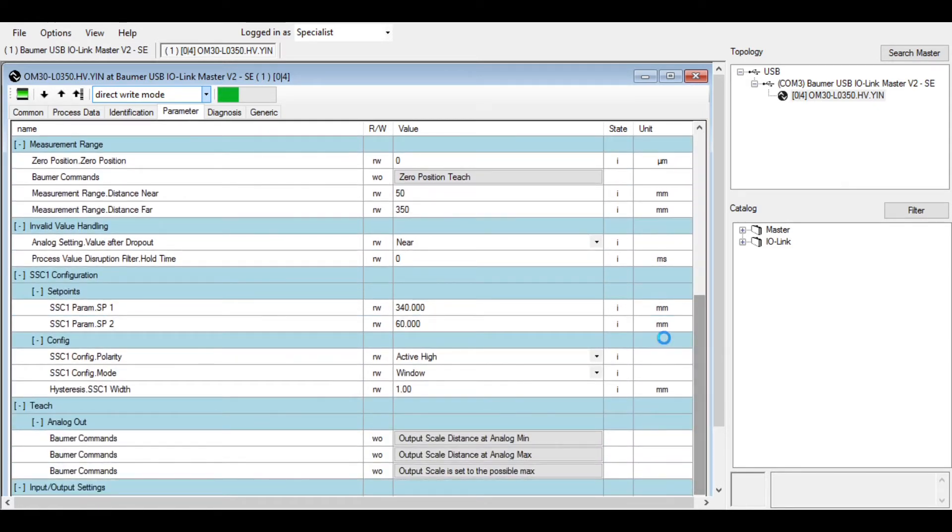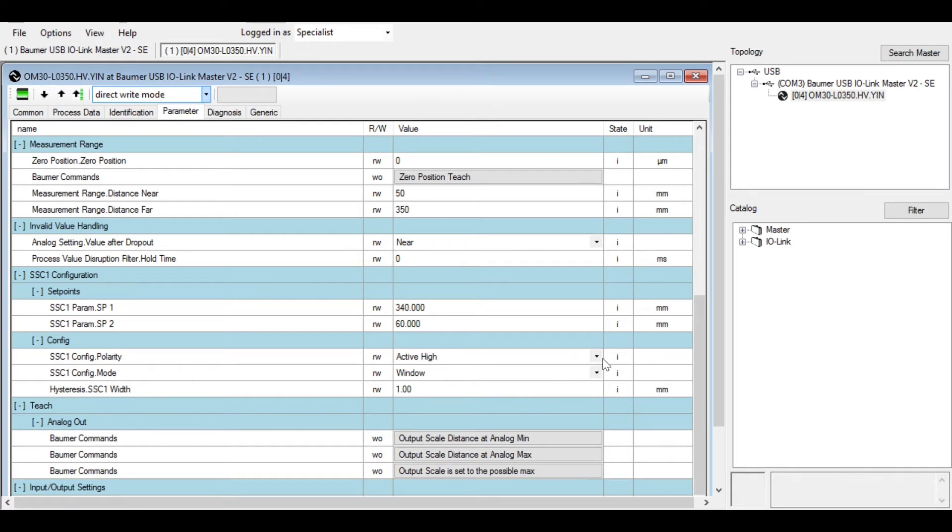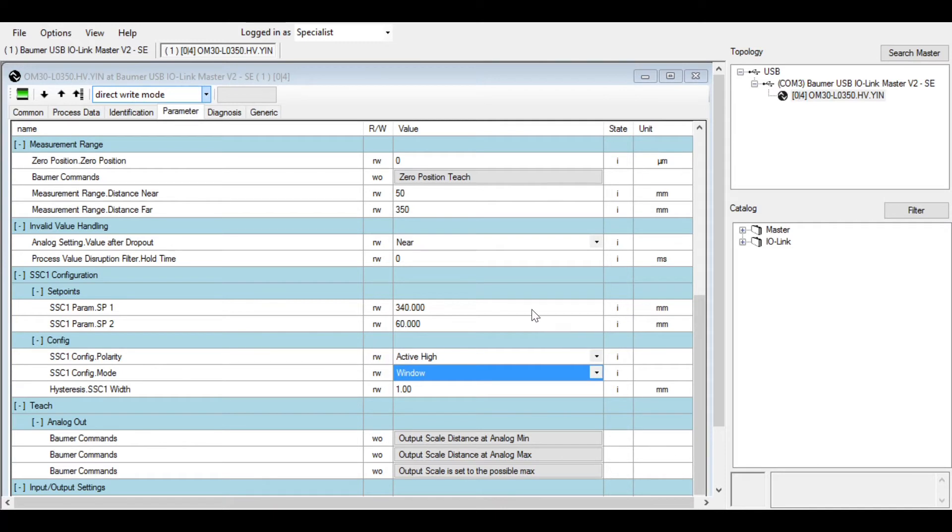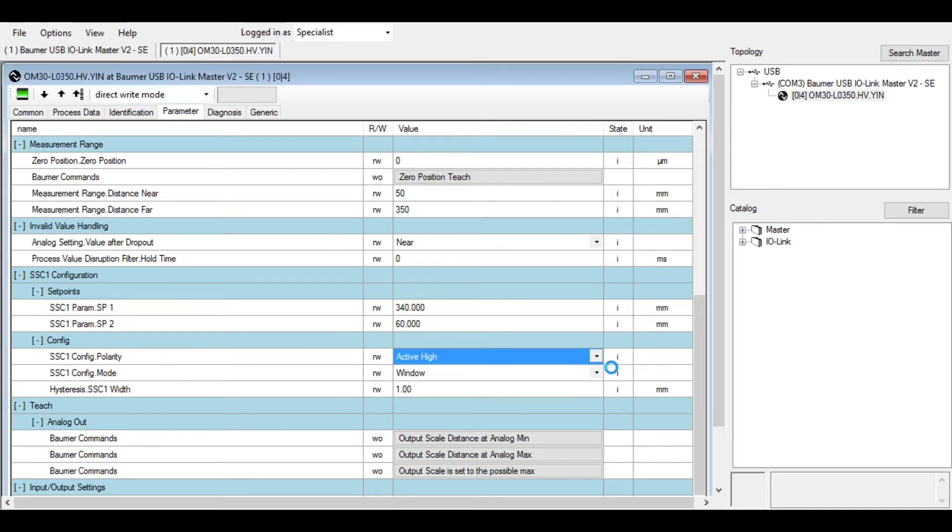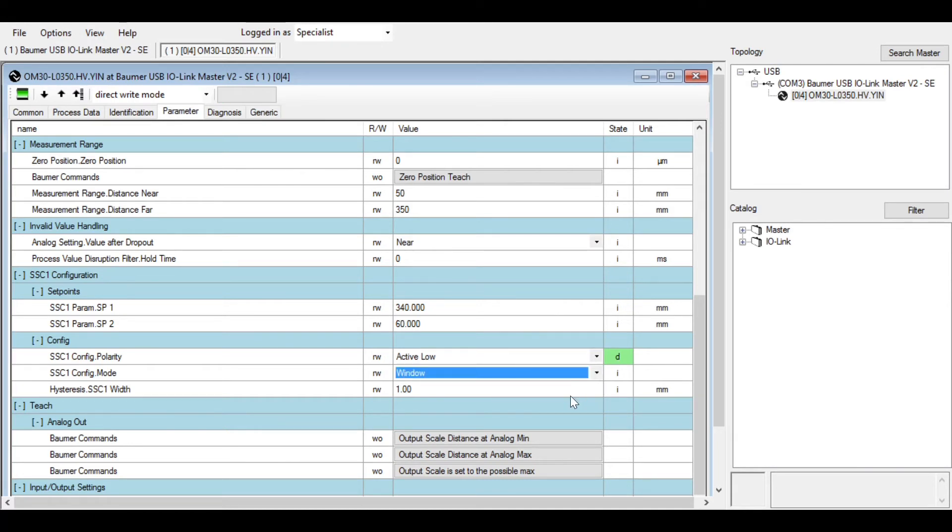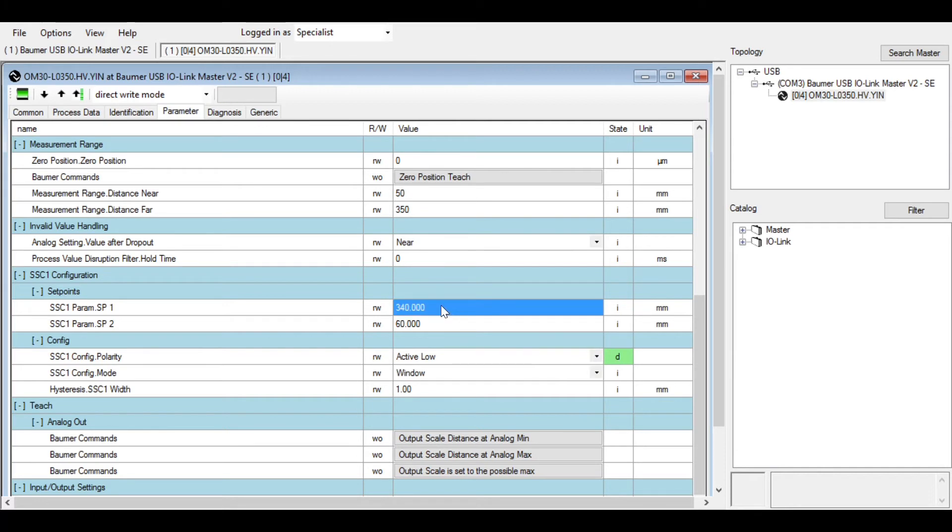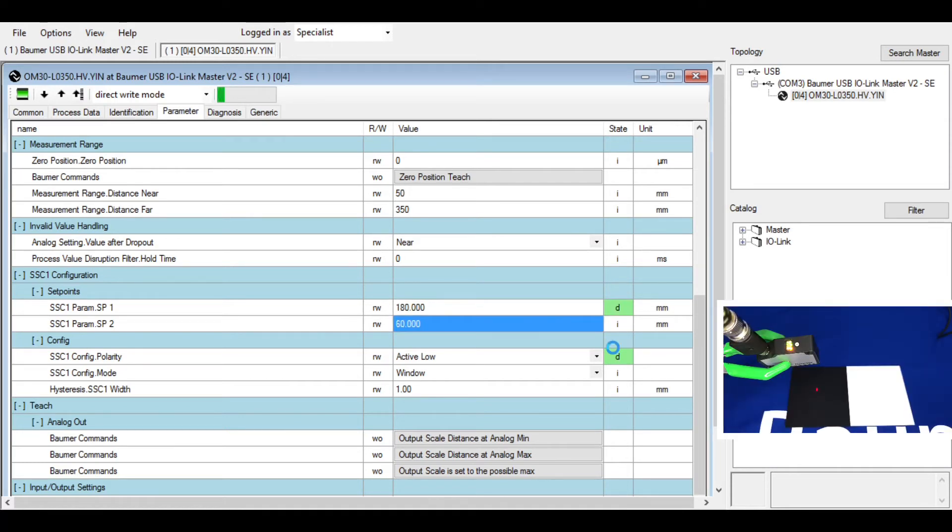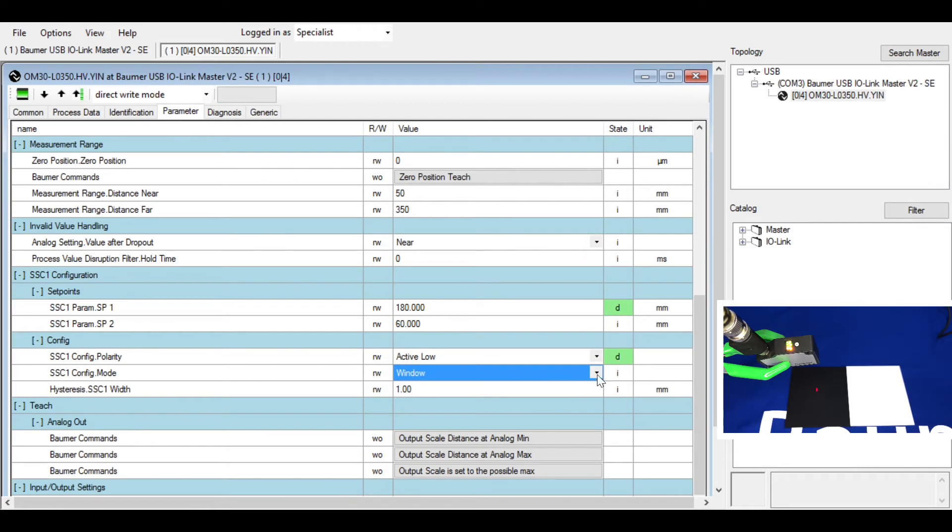Here you can set the actual switch point of the sensor, whether you want it on or off at a certain point or window. You can change it to active high or active low, and you can change it from a single point to window or vice versa. These are the switch points that you'd put in. If you wanted the output to come on at say 200 millimeters away from the sensor, or in our case say maybe 180 millimeters from the sensor, you can set it there and switch that to point.